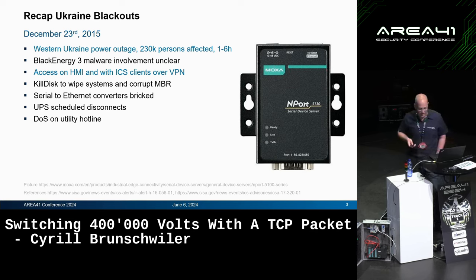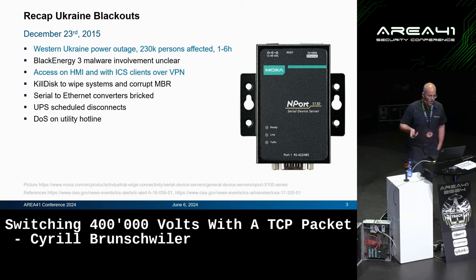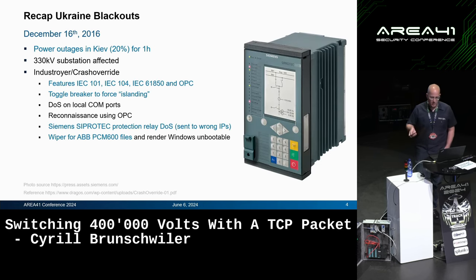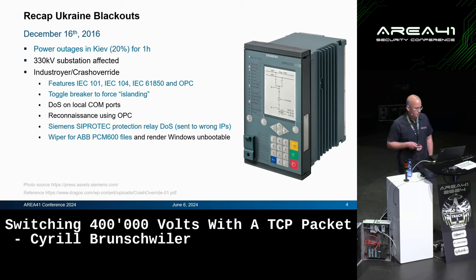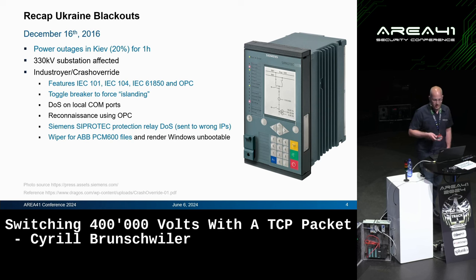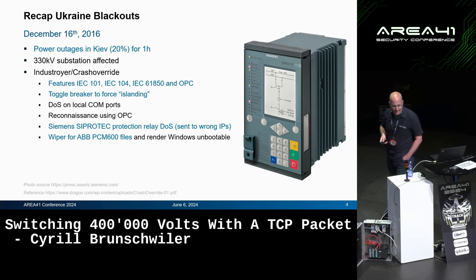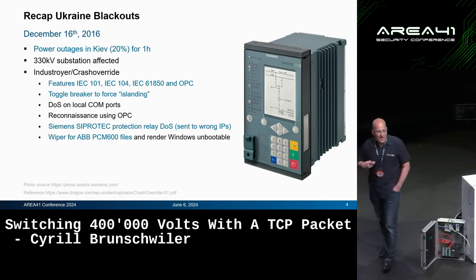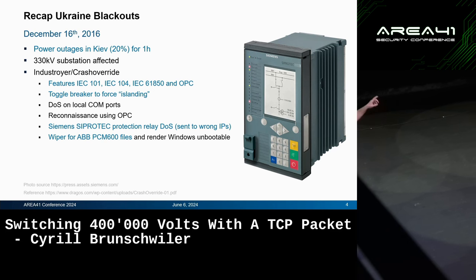They also did destructive things like corrupting firmware on devices — specifically the Ethernet-to-serial converters — so those wouldn't work anymore, making it hard to restore a substation. One year later, in December 2016, part of Kyiv went dark. They deployed a real dedicated malware that came with a ton of protocols, all with separate DLLs. They tried to toggle the breaker to force islanding, denial-of-service intelligent electronic devices like the Siemens Siprotec, and wipe PCM600 engineering files. My aim is to make you understand what this really means in the next 40 minutes.